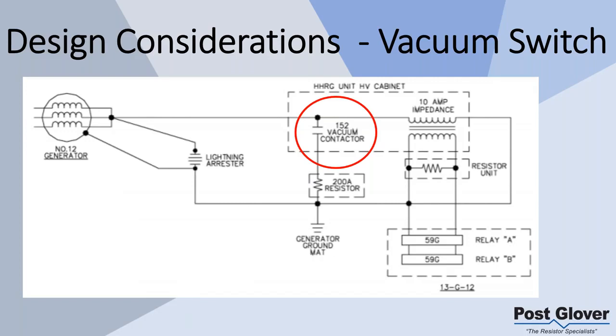In our example with the medium voltage generators, the multiple generators with just the LRG off the bus and the HRG on the generator, you may not need these things. You actually don't need to have a vacuum switch for that example. I want to go over the different ones, but I'm generally speaking about the single generator application with this. Once again, you can use that in a multiple generator application, but you don't have to.